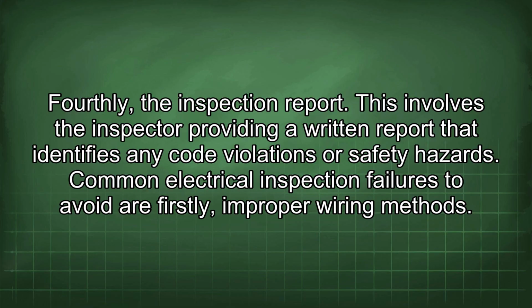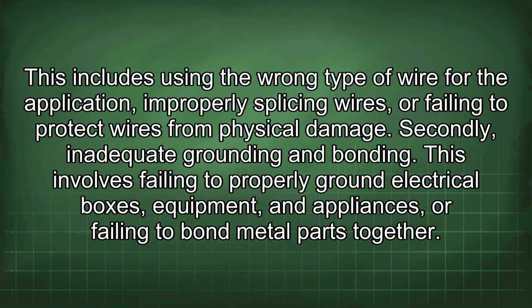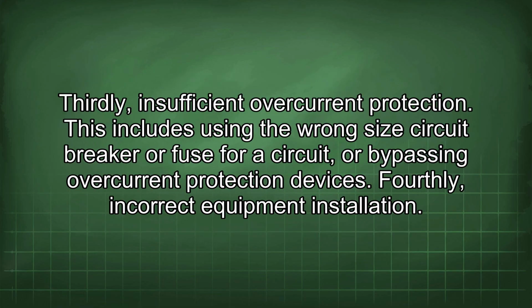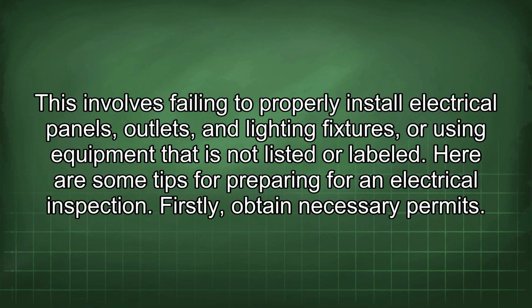Common electrical inspection failures to avoid are, firstly, improper wiring methods. This includes using the wrong type of wire for the application, improperly splicing wires, or failing to protect wires from physical damage. Secondly, inadequate grounding and bonding. This involves failing to properly ground electrical boxes, equipment, and appliances, or failing to bond metal parts together. Thirdly, insufficient overcurrent protection. This includes using the wrong size circuit breaker or fuse for a circuit, or bypassing overcurrent protection devices. Fourthly, incorrect equipment installation. This involves failing to properly install electrical panels, outlets, and lighting fixtures, or using equipment that is not listed or labeled.